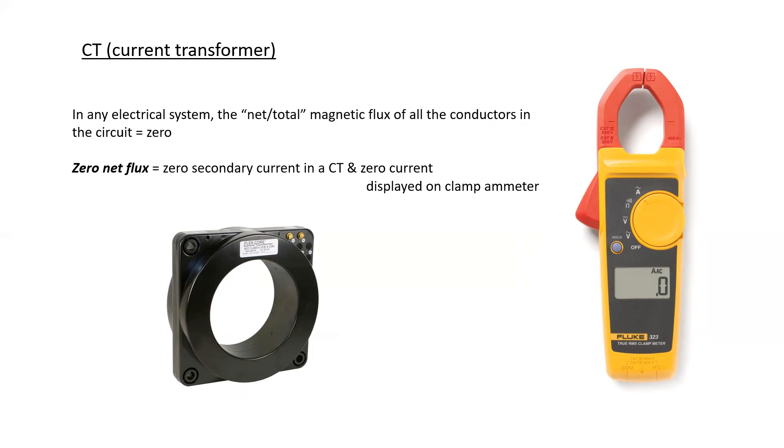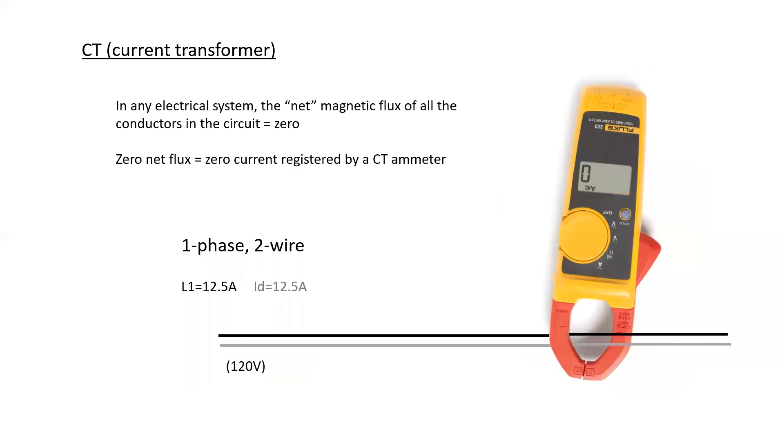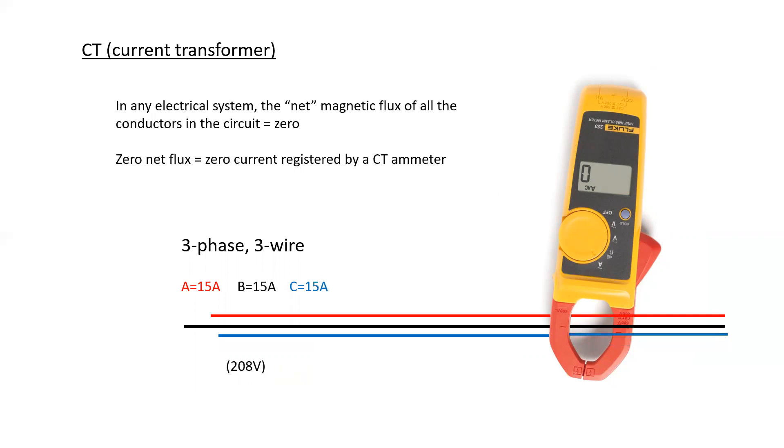Here's a few examples, not meant to memorize this. Here's a single phase two wire. What if you put both wires inside the clamp ammeter? You register zero amps. What if you put all three in there? Zero amps. What if you use a three phase four wire? Zero amps. And that's because the net or total, the sum of all of the magnetic flux, the vector sum of all of them is equivalent to zero at the very end, because we have all the conductors flowing through the same clamp.